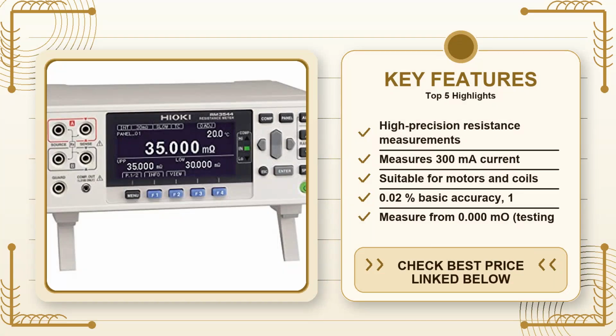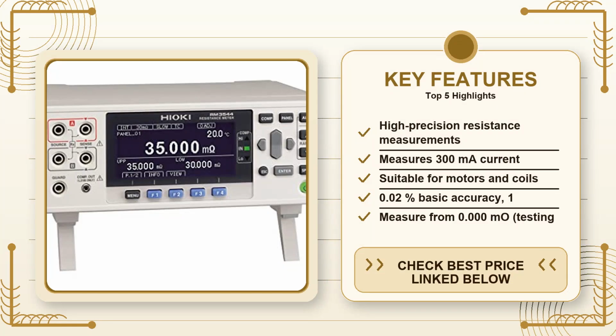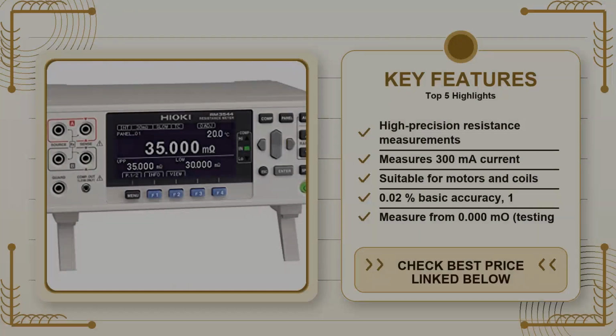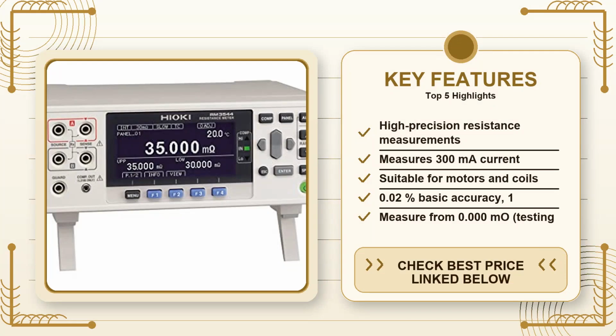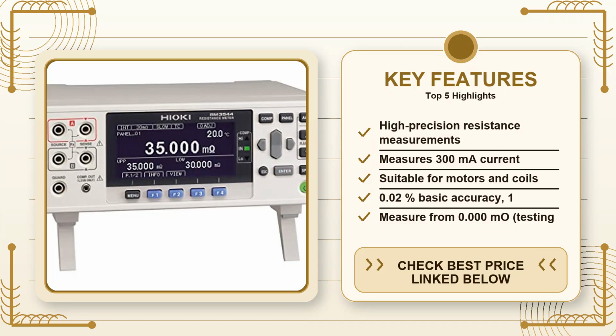The guard jack feature is another practical element that often gets lost in spec sheets. When you're measuring a low resistance, the probe can pick up stray currents that skew the reading. Connecting the guard jack effectively isolates the measurement path, cutting down on that error. I've seen field techs forget to engage the guard and end up with a reading that's a few percent high, then waste an hour hunting a problem that isn't there. The RM3544 makes the guard jack easy to attach, which is a subtle time saver that you only notice when the alternative is a messy workbench.